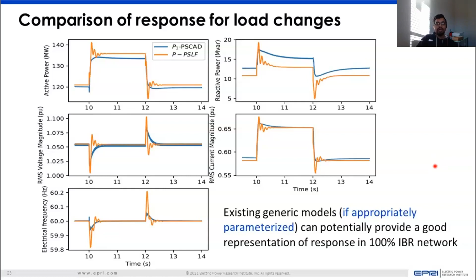With this kind of constant frequency control, or this distributed slack bus perspective, where frequency returns to nominal value within a few seconds of a disturbance, a legitimate question is what would balancing authorities do? Our present concepts of secondary frequency control depend heavily on frequency deviation and settling at an off-nominal value, along with change of flow along tie lines between two areas, which is then used to bring the frequency back to nominal and let each control area take up its disturbance. So we implemented our constant frequency control across multiple areas of the network, and found that just by looking at tie line flow, you can still get the same form of secondary frequency control properties, with frequency already being at nominal.